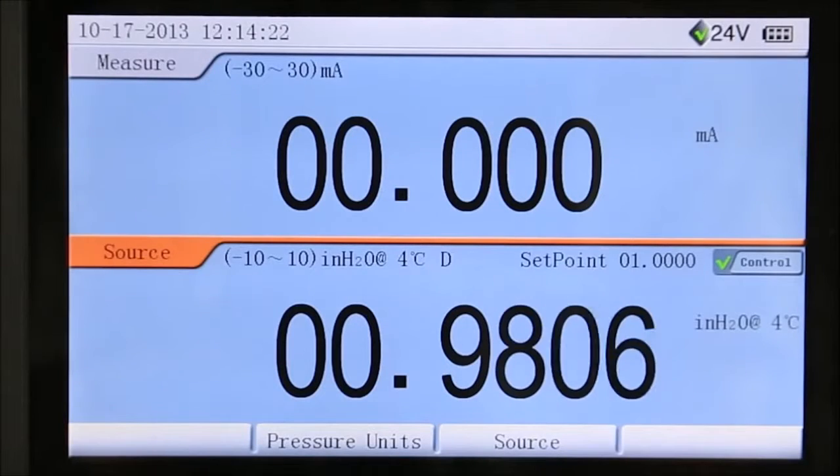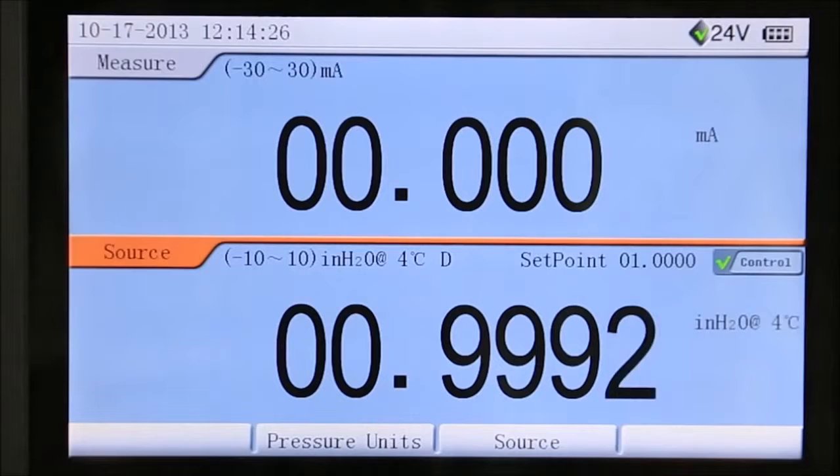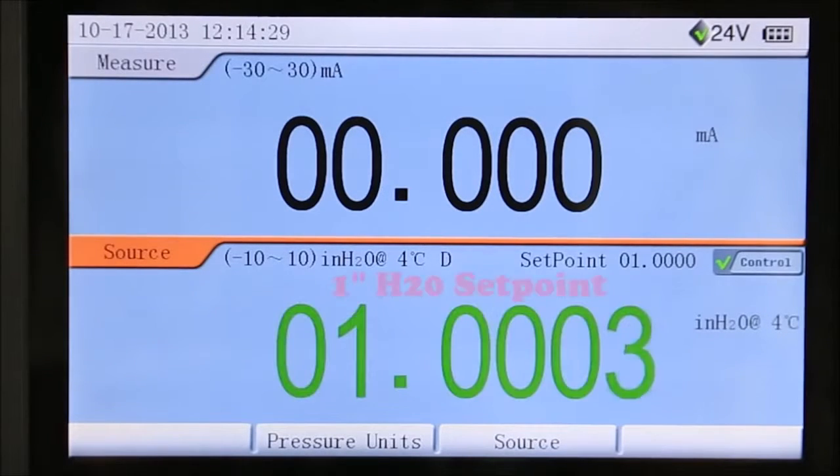The low pressure model 761-LLP has internal ranges of 1 and 10 inches of water, ideal for testing draft range and HVAC sensors. Control precision is better than 1 ten-thousandth of an inch of water.